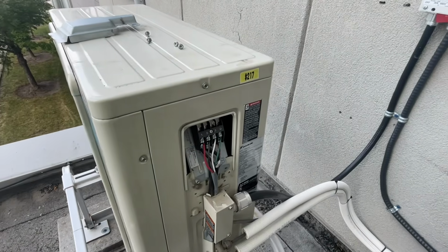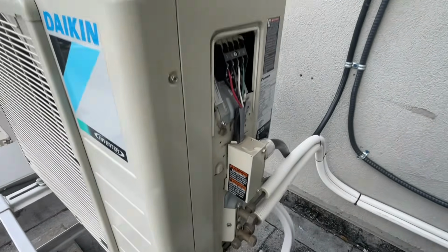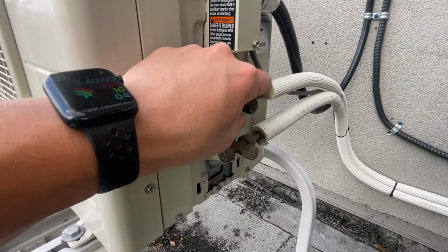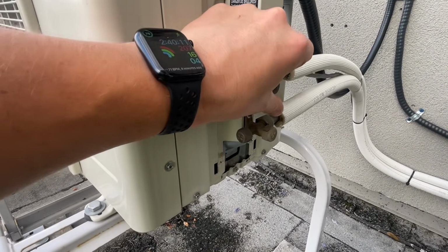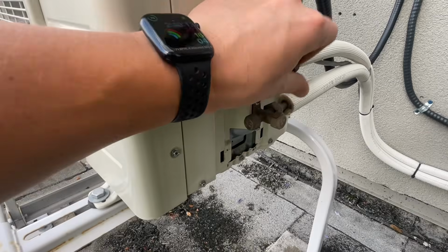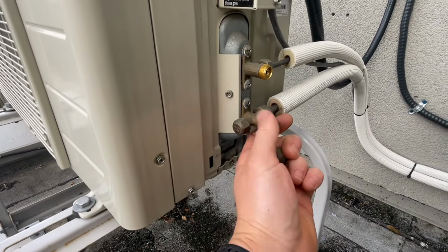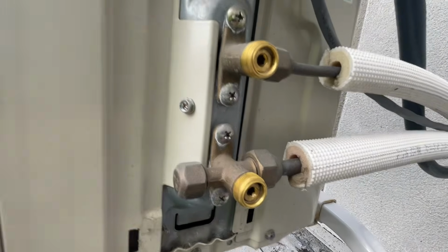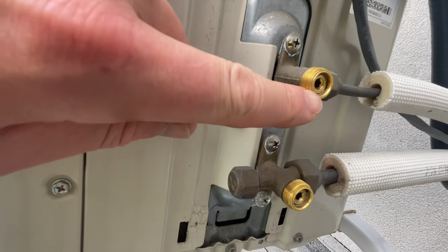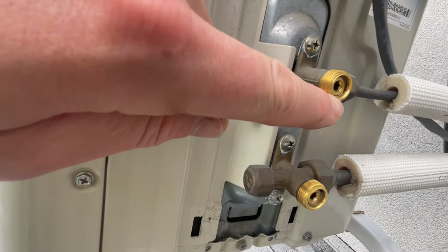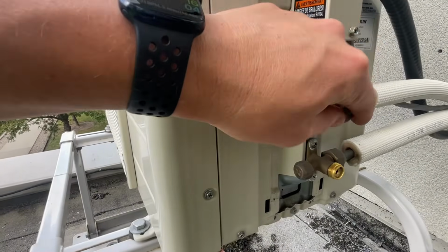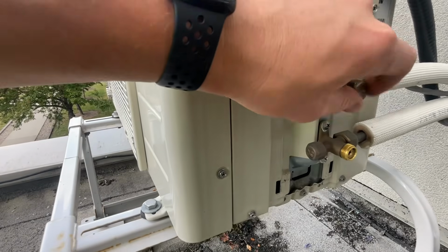So according to our troubleshooting chart, our first step here is going to be to make sure our stop valves are open. So what they mean by that are these service valves on the unit here, which will shut off flow from the condenser to the evaporator. I know these are fully open. As you can see, they're all the way back seated here. If they were deeper in and threaded forward, we would know that they were actually closed, which they're not. So we're good there.